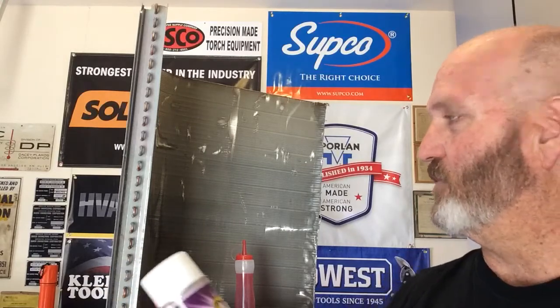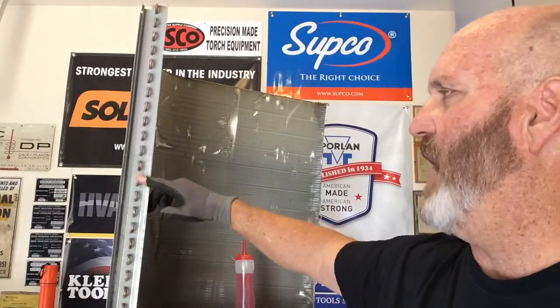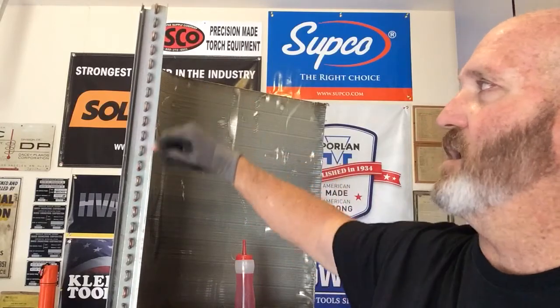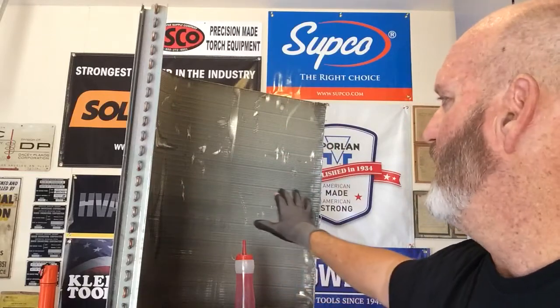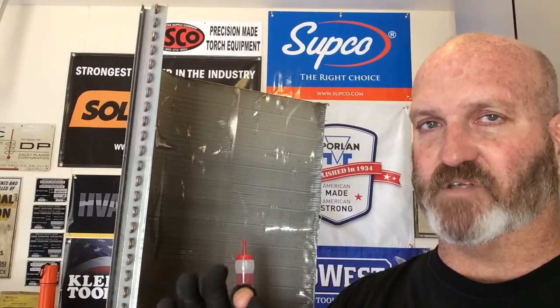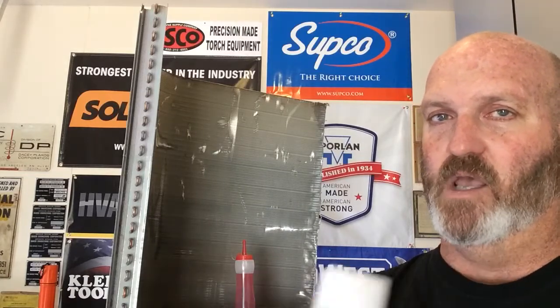So the Coil Coating — I had a hard time with that — the Coil Coating has actually been sprayed. I sprayed it about halfway up, so right in this area down it's all Coil Coating, and up here is uncoated galvanized. I've also sprayed the coil as well. I wanted to see how it bonded to the fins and make sure it did not fill in the gaps between the fins, because sometimes I'm always worried these things will come out like spray glue and pack the coil in. Well in this case it didn't do that at all.